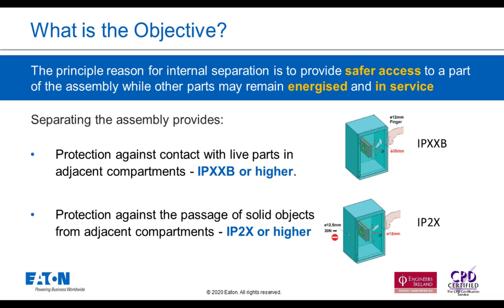So the main objective is to provide a safer environment for somebody gaining access to part of an assembly while other parts remain energized or live. Separating the assembly does this. The first thing is that by separating it, we provide protection against contact with live parts in adjacent compartments. And this is normally done by creating an environment that is IPXXB in terms of its IP rating. Basically, in the industry, we would call that fingerproof. And secondly, there is protection against passage of solid objects. Obviously, the benefit of this is that if you're in a compartment doing some maintenance, it reduces the risk of objects falling through the compartments and potentially causing an arc flash.